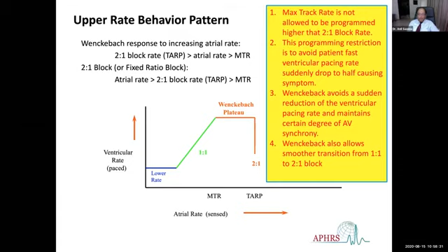So we need to program this. This was a young man, a 16, 17-year-old boy. So we have to program the upper rate to about 150, 160, 170. But at the nominal settings of AV delay and of the PVARP, that may not be possible, because these things consume time in the cardiac cycle. AV delay is about 150 to 200 milliseconds, and if we program the PVARP to about 250 to 300, the total may become around 500. That limits the upper tracking rate to 120. So we have to somehow decrease these delays.